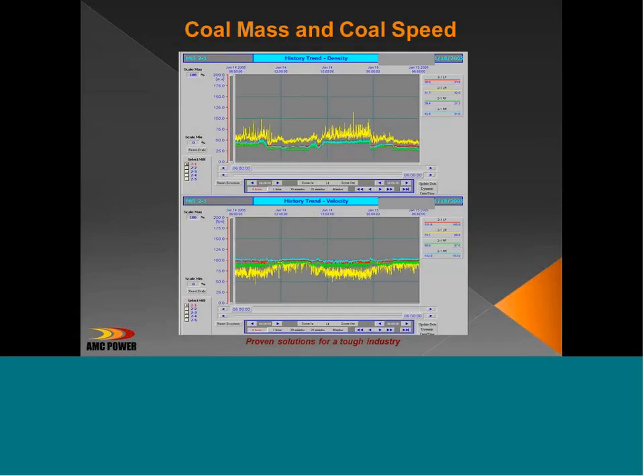Now, again, to get to that mass flow measurement, we measure mass, what we call density, because it's the mass of coal between the two sensors, mass per volume of pipe, and the speed. What you see here is those measurements over the same 24 hours. The top screen is the mass of coal, and the bottom screen is the velocity of coal. And going back to our coal slip issue, this is a real telling screen because we see that the milling system is throwing much more coal to the yellow pipe than the other pipes.